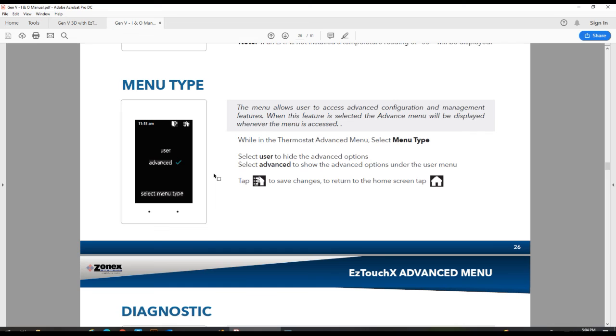Alright, once you've configured and set everything up, you want to go ahead and adjust your menu type to user. There are a lot of times we get calls at tech support where the end user's gone into the thermostat, made adjustments, and now the thermostat doesn't seem to be quite working. So go ahead and make those adjustments and change it to user, and then this will hide all the advanced menu options so the customer can't change anything and screw up your configurations.